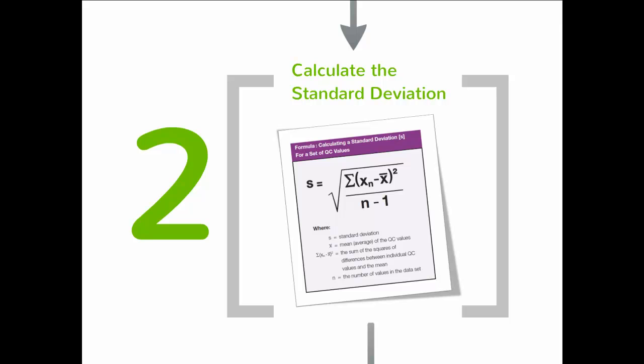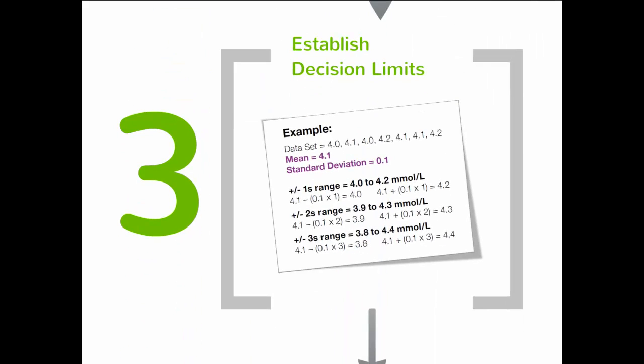Using the mean and standard deviation, the laboratory can establish decision limits. These limits are used to define what is considered an acceptable control result. Decision limits are established at plus or minus 1s, 2s, and 3s from the mean.